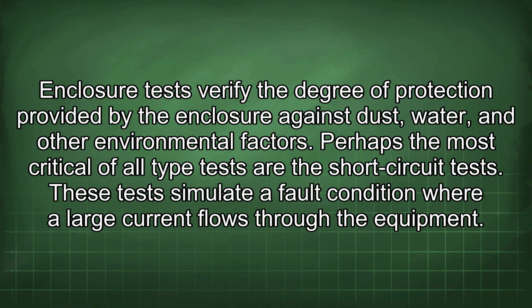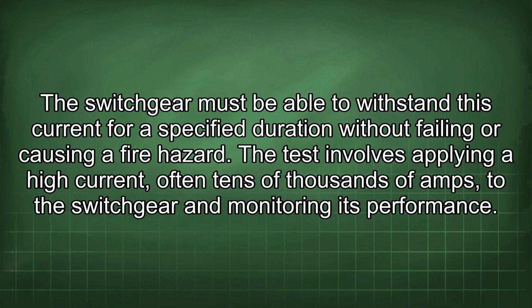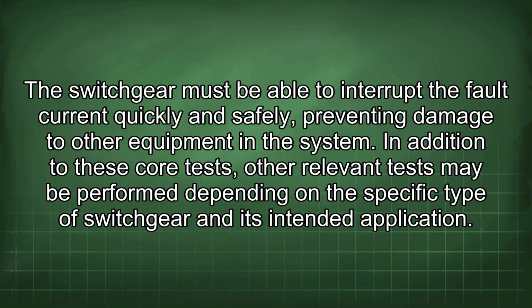Perhaps the most critical of all type tests are the short-circuit tests. These tests simulate a fault condition where a large current flows through the equipment. The switchgear must be able to withstand this current for a specified duration without failing or causing a fire hazard. The test involves applying a high current, often tens of thousands of amps, to the switchgear and monitoring its performance. The switchgear must be able to interrupt the fault current quickly and safely, preventing damage to other equipment in the system.